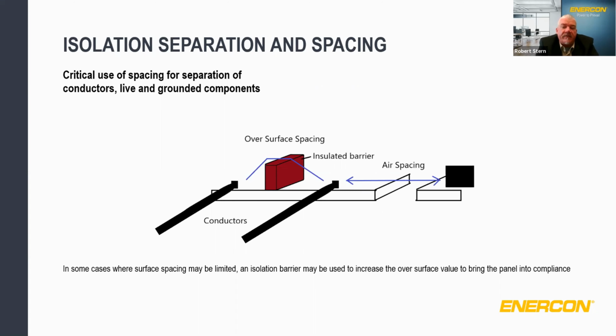Between uninsulated live parts and ground or dead metal. Again, there's a real concern about arcing there. Between uninsulated live parts and enclosure surfaces. This would be the interior enclosure surfaces, so from the enclosure wall. And between field terminal wires. In some cases where the surface spacing may be limited, an isolation barrier may be used to increase the over surface value to bring the panel into compliance. Next page, please.